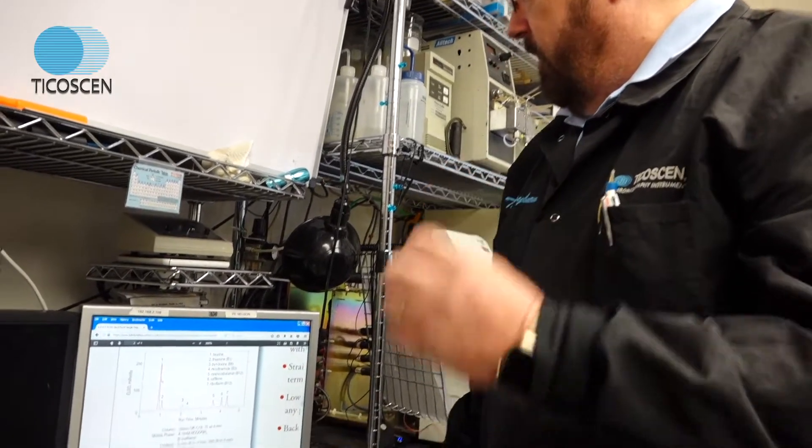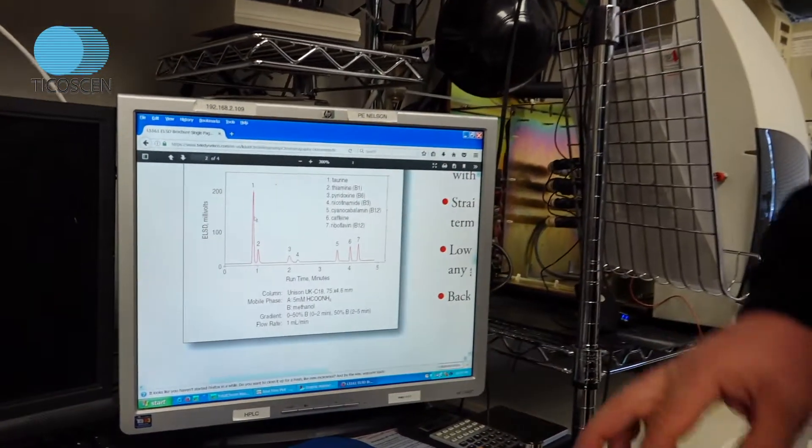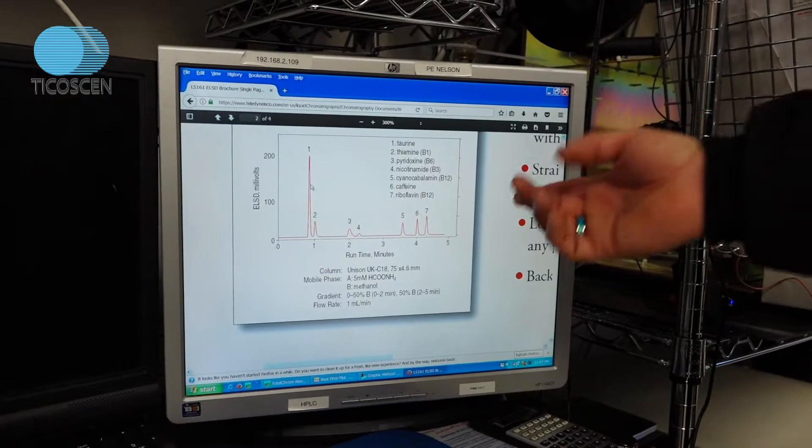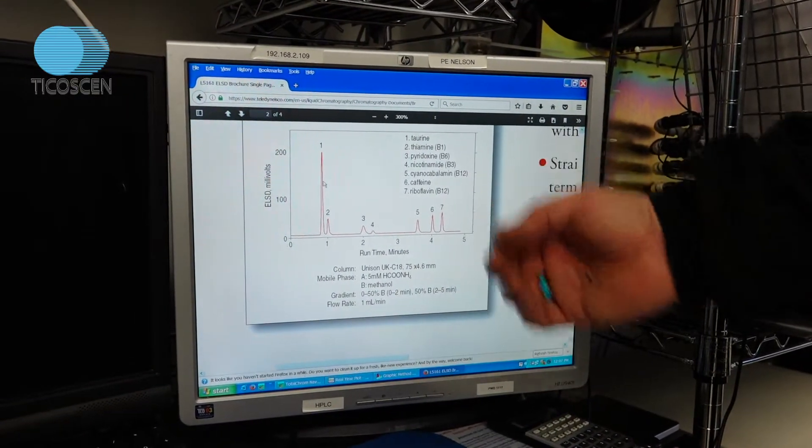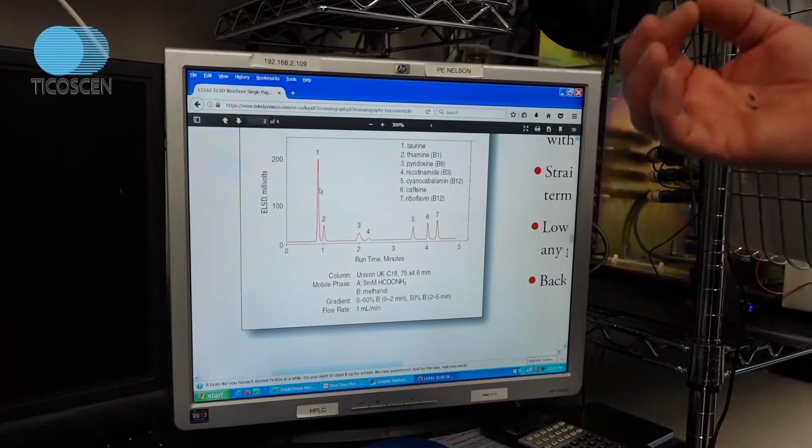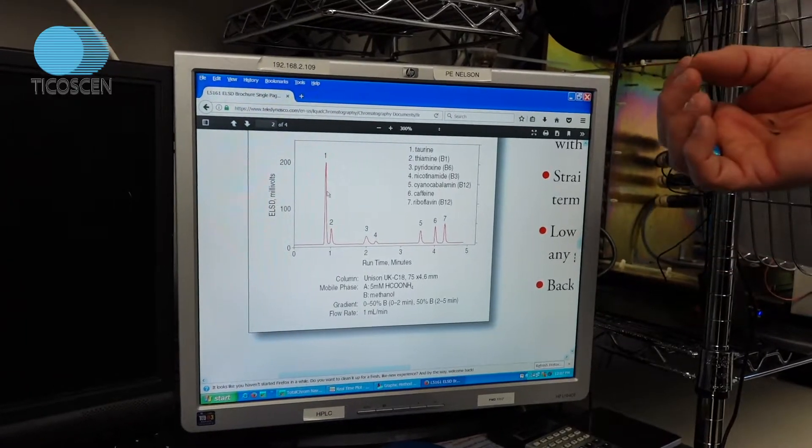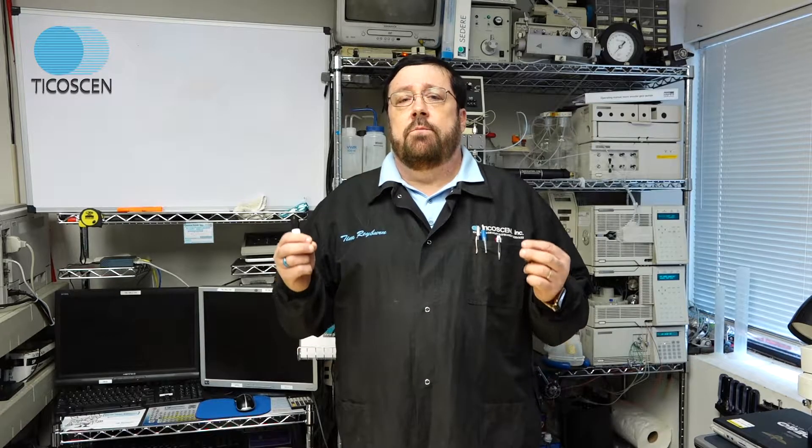And a major mass could have very low chromophore and you get a small response. So UV could mislead you in the actual response and purity of your compound. You can be better assured with ELSDs you're going to get a mass proportional purity compound. So you can assure that your product purity is correct. You can assure that your product percentage mixture is correct. Your quality control mixtures are at the proper balance because it's mass proportional and non-specific. The response will be mass proportional on the ELSD.